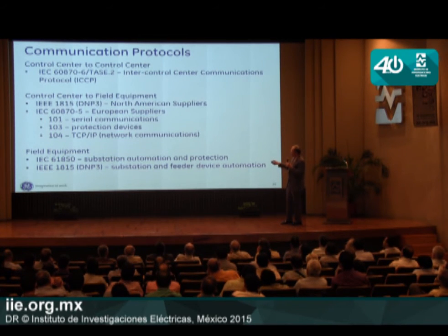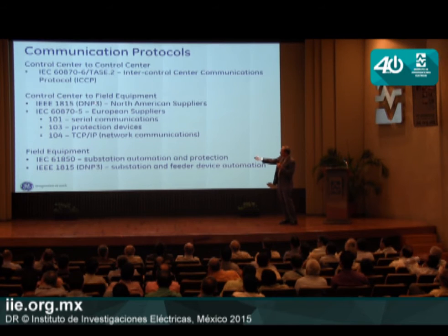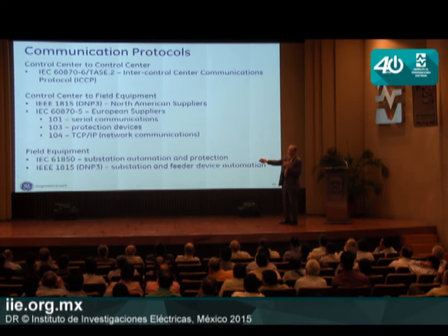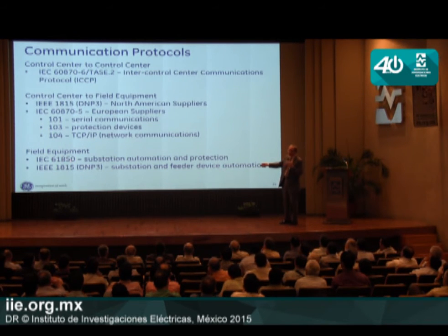One standard. From control center to field equipment, there are really two standards: in North America, DNP3, which is IEEE 1815; for European suppliers, IEC 870-5, with 101 for serial communications and 104 for network. In the field, it's typically IEC 61850, the worldwide standard for substation automation, communications, and protection, along with DNP3.